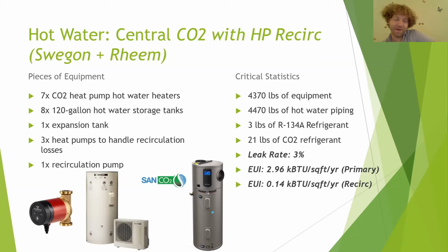So, the limitation with the CO2 heat pumps is that they don't want to see the recirculation water. And when you use a central system, you need recirculation water. You can't just let the water get cold in those pipes. You need to move it around. They have smarter ones now where they actually learn from the building. So that's pretty awesome, and so we can minimize the energy of the recirculation loop. There's a bunch of strategies for that. That's a whole presentation in itself. But we have to heat that water back up, because that water comes back at 95, 100 degrees. We've got to heat that back up to 120.